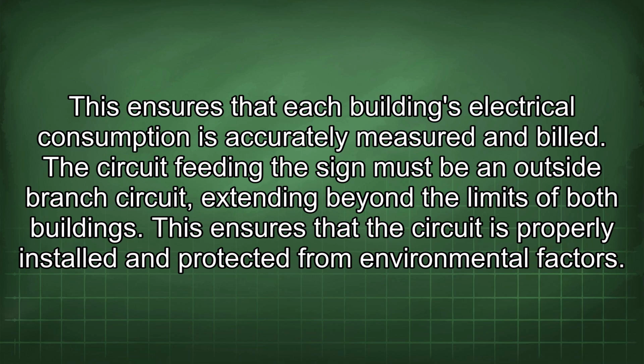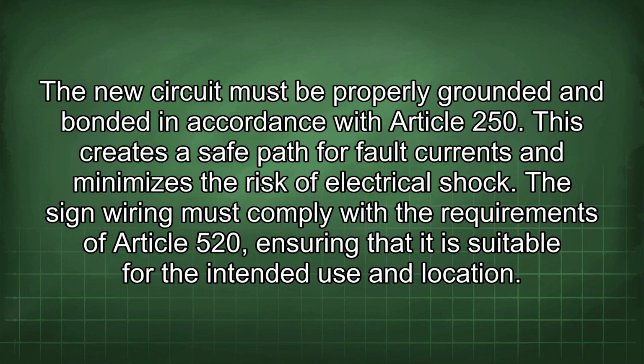The circuit feeding the sign must be an outside branch circuit, extending beyond the limits of both buildings. This ensures that the circuit is properly installed and protected from environmental factors. The new circuit must be properly grounded and bonded in accordance with Article 250. This creates a safe path for fault currents and minimizes the risk of electrical shock.